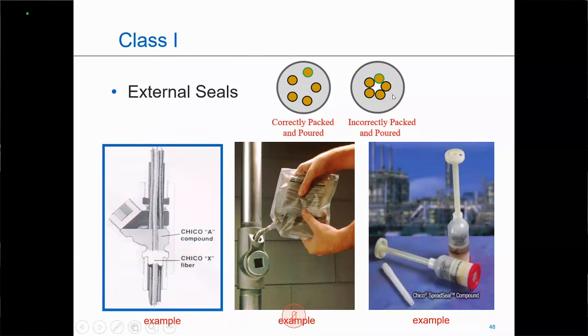Here was an example if somebody just grouped the cables together in a bundle and then poured the compound, it would just go around the outside. And here's an area where gases and vapors could escape right through where all those circular edges come together. And so that would be an incorrectly poured fitting. The gases could migrate through my conduit system. The explosion could travel through my conduit system. So it's critical for safety to make sure that we have each and every individual conductor separated and the compound is around each one.